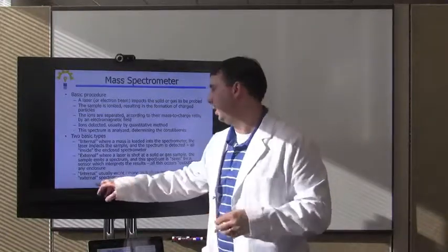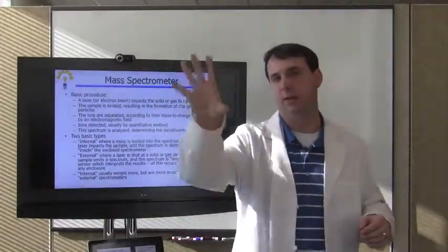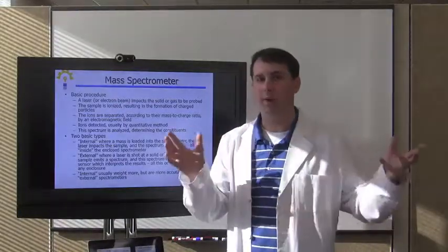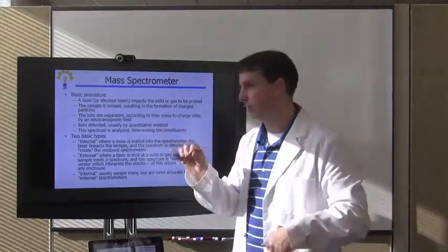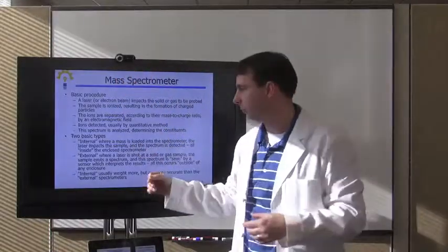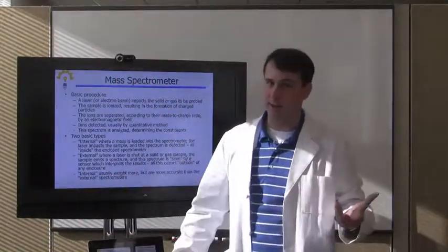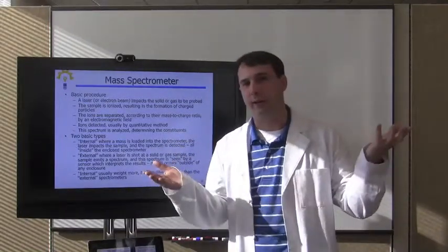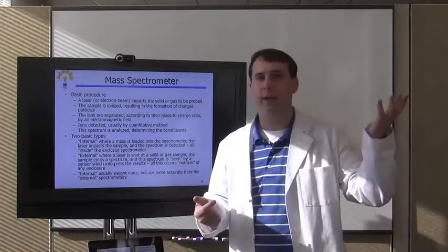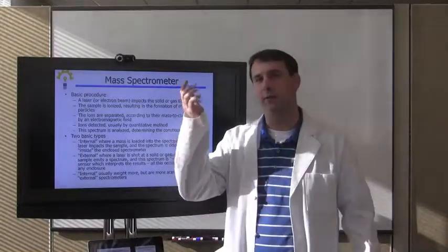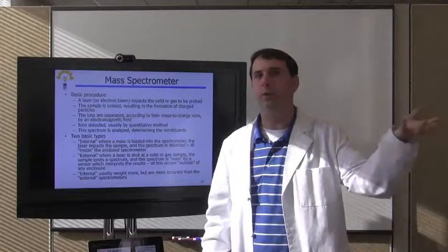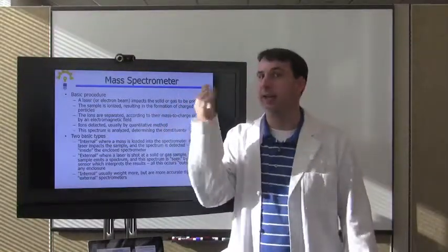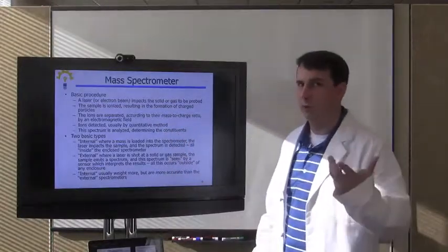The external ones, where it shoots a laser outside and it fluoresces outside, are less accurate for obvious reasons, because there's control issues and stuff, and it's outside in the light or whatever. But they weigh less, and they're easier to use because you don't have to put it inside of a box. So there's a trade there: a more accurate, heavier, and more difficult to use device versus a lighter, less accurate, and easier to use device. So you can decide which one you want to use later.